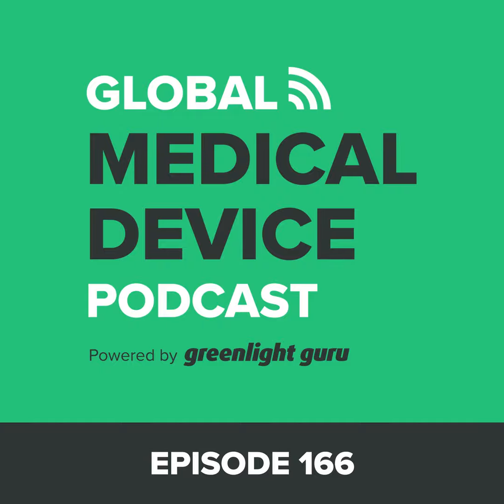Well, once again, I don't want the audience to misunderstand what we're saying, or let me not speak for you, Jon. What I'm saying, I'm not suggesting that we should not use labeling as a form of risk mitigation. We certainly can. But it's only one piece, and it shouldn't be the only piece. As I said before, ISO recommends, and I strongly agree, that it should be the risk mitigation of last resort. We should do everything else that we can, short of labeling, to mitigate risk. And I'll give you a perfect example, Jon, and I think this is going to lead us right into the discussion of the second guidance, and that is on nitinol.